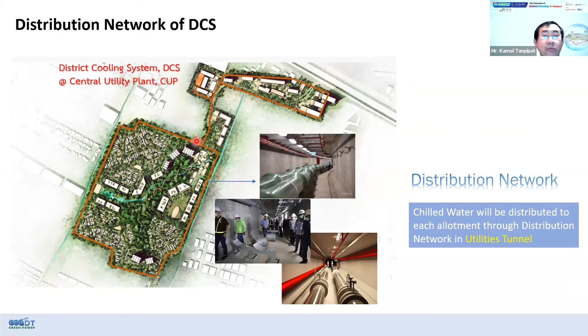Allow me to touch a bit upon the benefits, in terms of figures, that we get from implementing the DCS system for the Forestier project itself. As I mentioned, there are a lot of benefits, and one of them is on the infrastructure side, the installed capacity. For the installed capacity, we calculated that using a conventional air conditioning system for the project might need up to 22,000 refrigerant tons. But because of load sharing, the installed capacity using the DCS can be down to 20,000 tons, which is the size of the Forestier project itself. In terms of energy consumption and GHG emission, because of the performance of the DCS system, it is a lot better than the conventional systems.